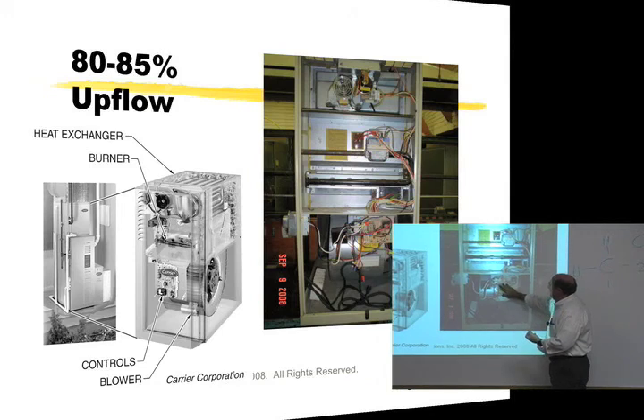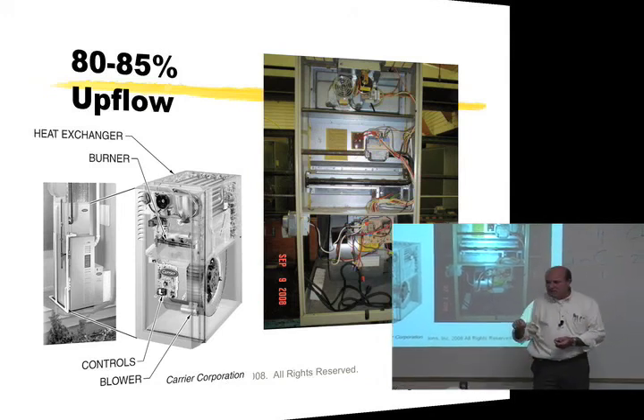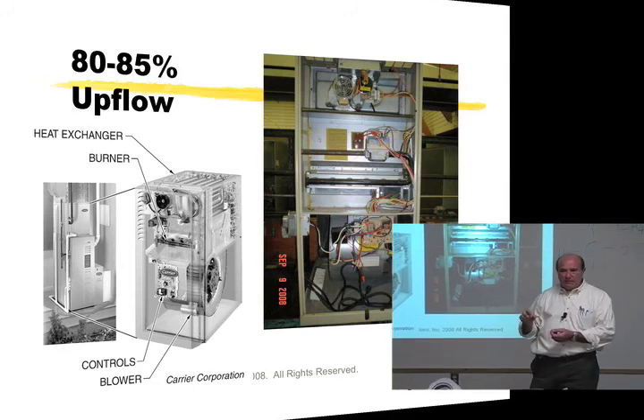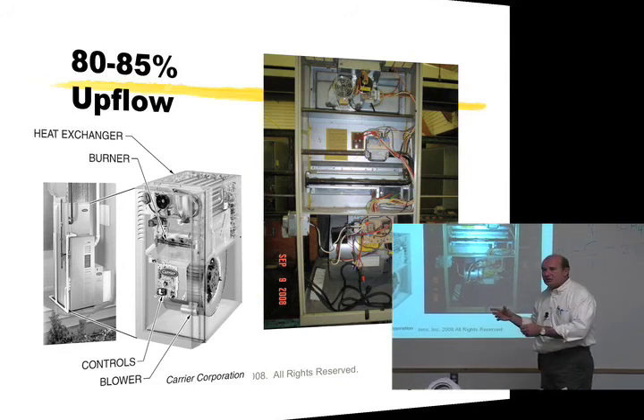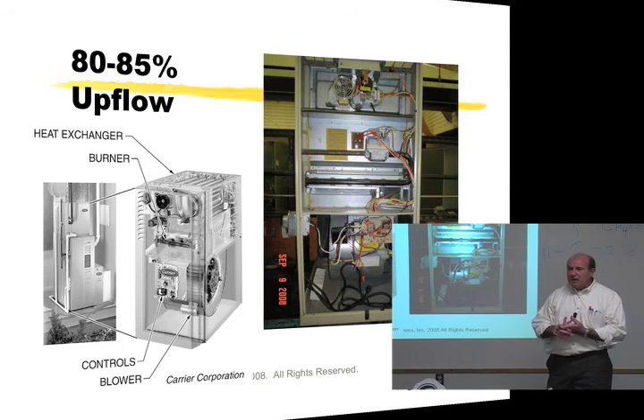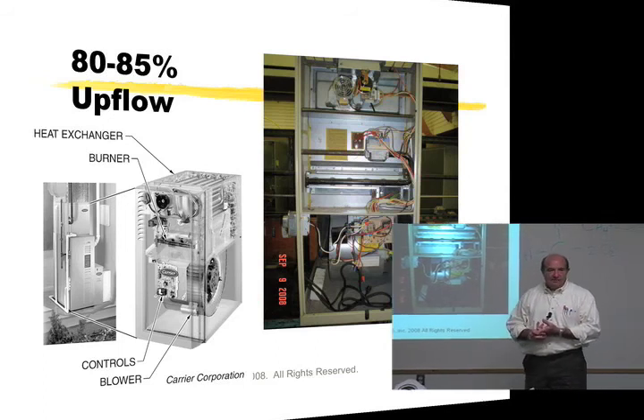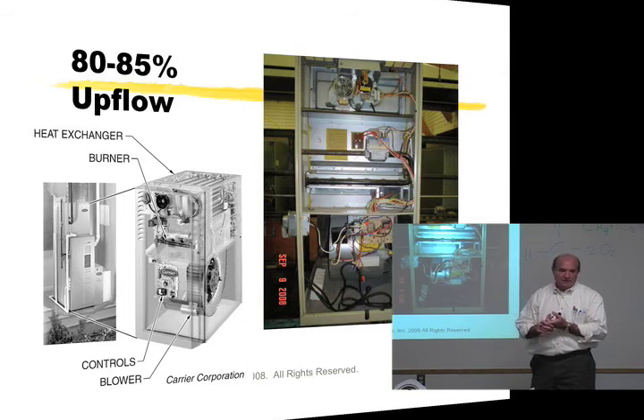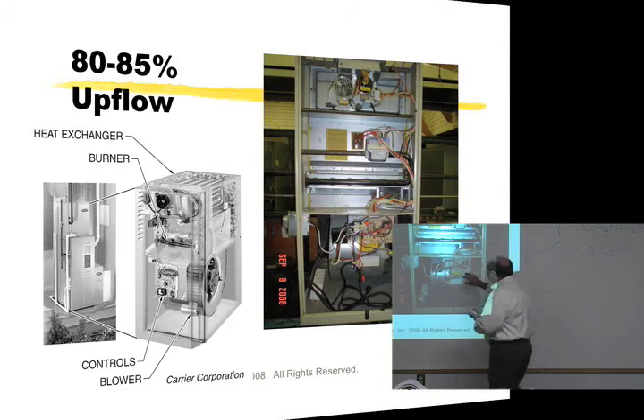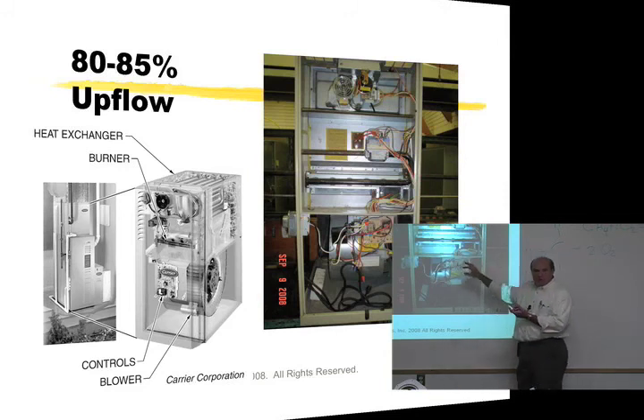They'll also have a location on this board where you can change the blower speeds. Now most of the supply blowers, the blower motor that delivers air to the house in a direct drive furnace, they'll be multi-speed blowers. Minimum, they're always at least 2-speed. I've seen them as much as 5 speeds. But the circuit board in here usually gives you 2 speeds to play with. There'll be one for cooling mode, one for heating mode.